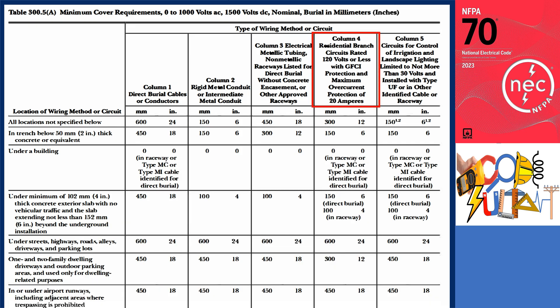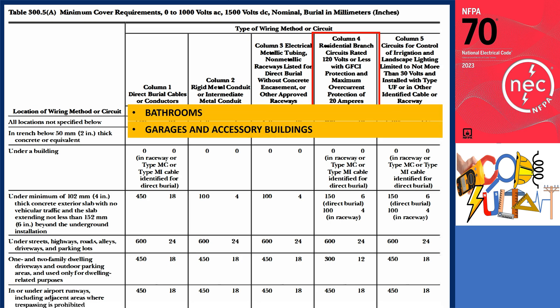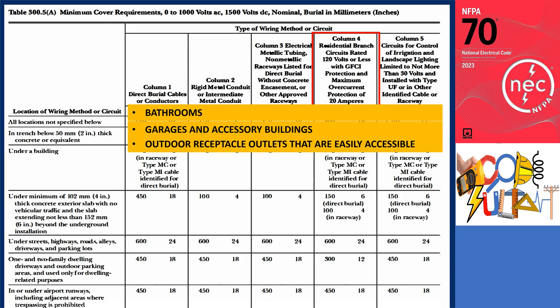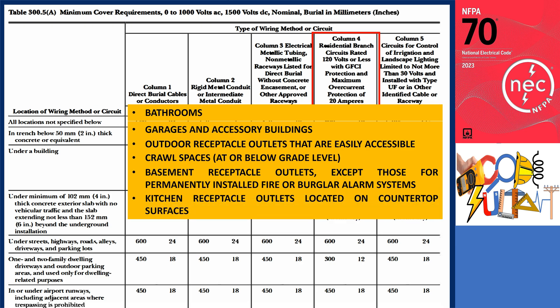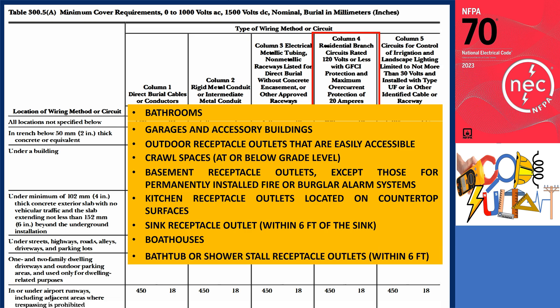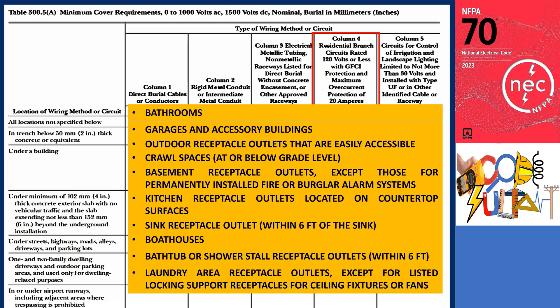Column 4 is designated for residential branch circuits rated at 120 volts or less, equipped with GFCI protection and a maximum overcurrent protection of 20 amperes. Examples include bathroom receptacle outlet wirings, garages and accessory building receptacle outlet wirings, outdoor receptacle outlet wirings that are easily accessible, crawl space receptacle outlets at or below grade level, basement receptacle outlet wirings (except those for permanently installed fire or burglar alarm systems), kitchen receptacle outlets on countertop surfaces, sink receptacle outlet wirings within 6 feet of the sink, boathouses wirings, bathtub or shower stall receptacle outlet wirings within 6 feet, laundry area receptacle outlet wirings, indoor damp and wet location receptacle outlets, and any residential branch circuits rated 120 volts or less with GFCI protection and maximum overcurrent protection of 20 amperes.